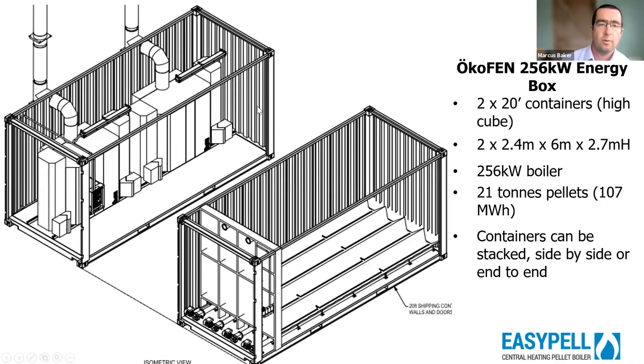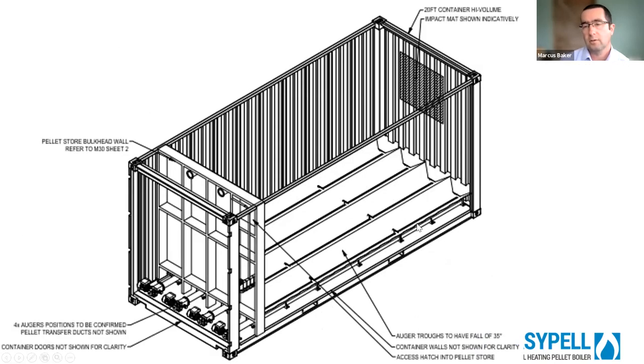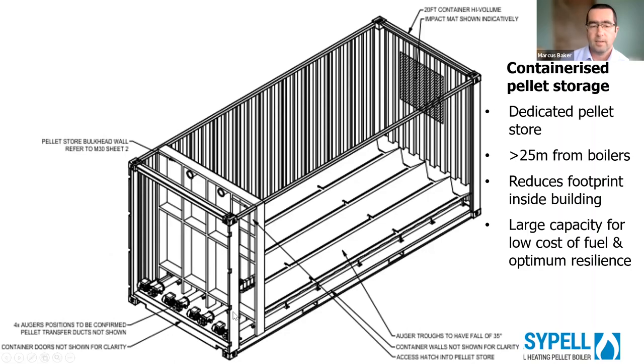The containers can then be end to end, side by side, or on top of each other. On top's going to add some cost, and you'd actually have the boilers on top of the pellets most likely because of the weight ratio. But then you're going to have steps and so on, but it's all eminently doable. And you could just use a 20 foot container for pellet storage. It's something we're going to look at in a minute. They can be up to 25 meters, just using a standard on-boiler suction system, from where the boilers are placed. And so then you can reduce your footprint inside the building, and you've got a large, low cost, high capacity, weatherproof store that just gets plugged in essentially.